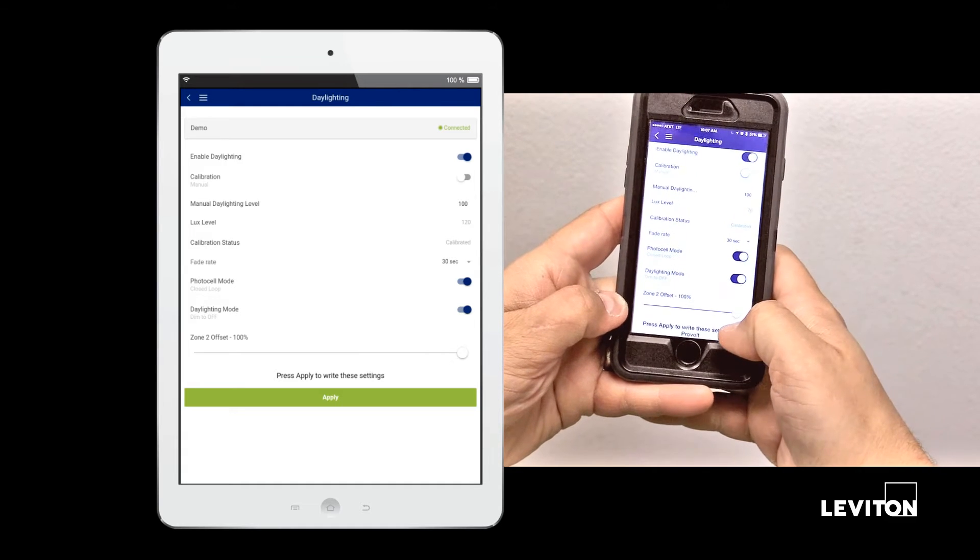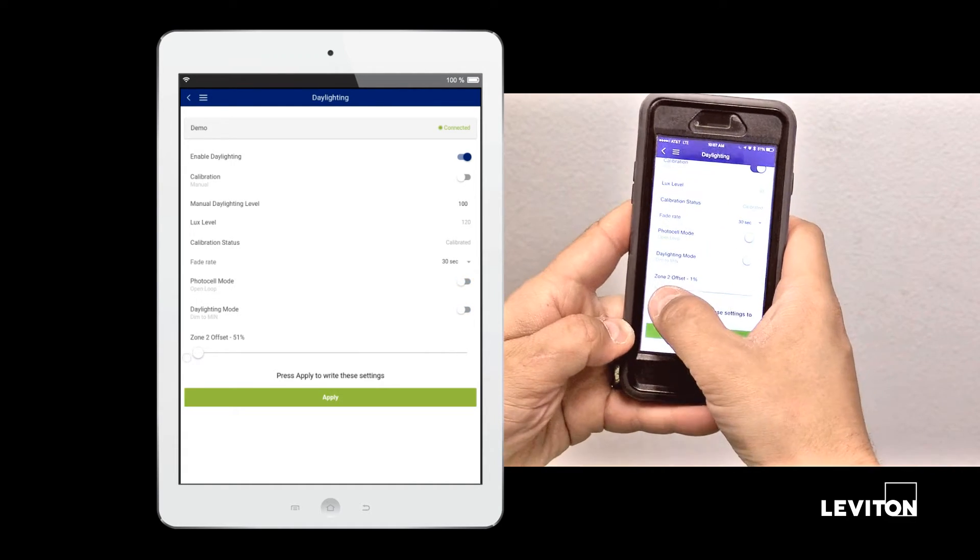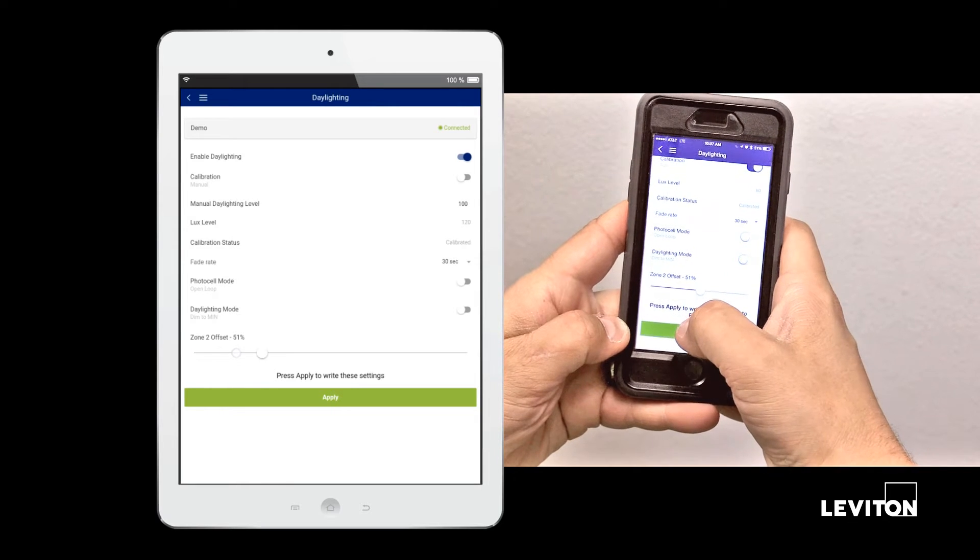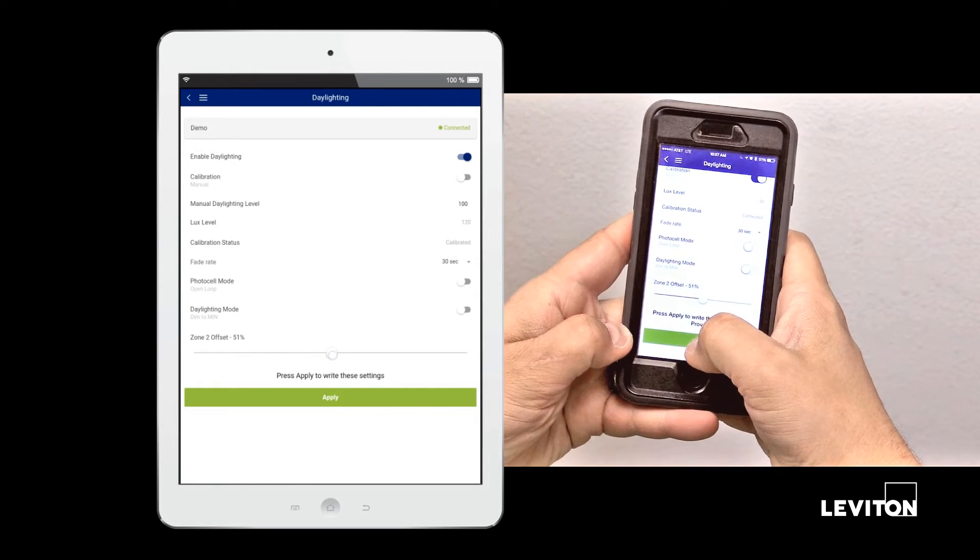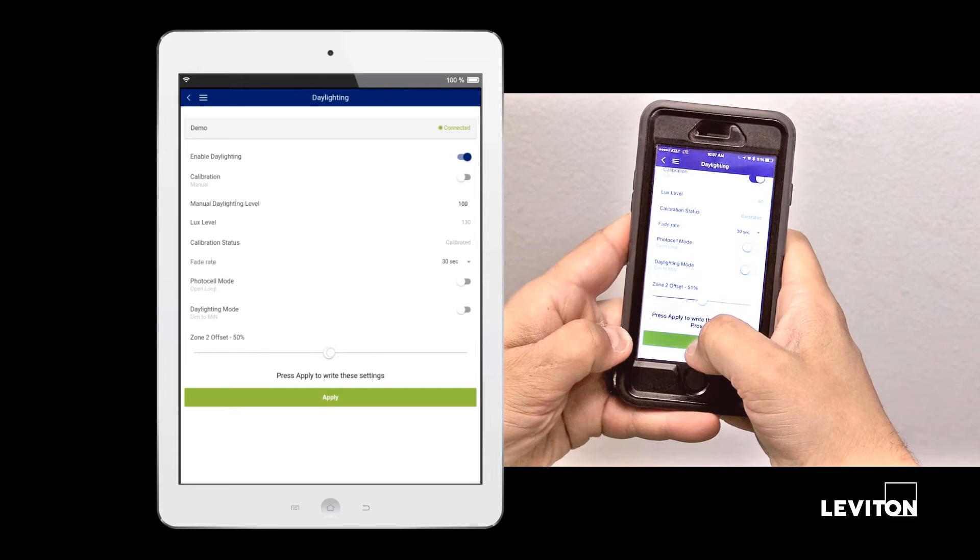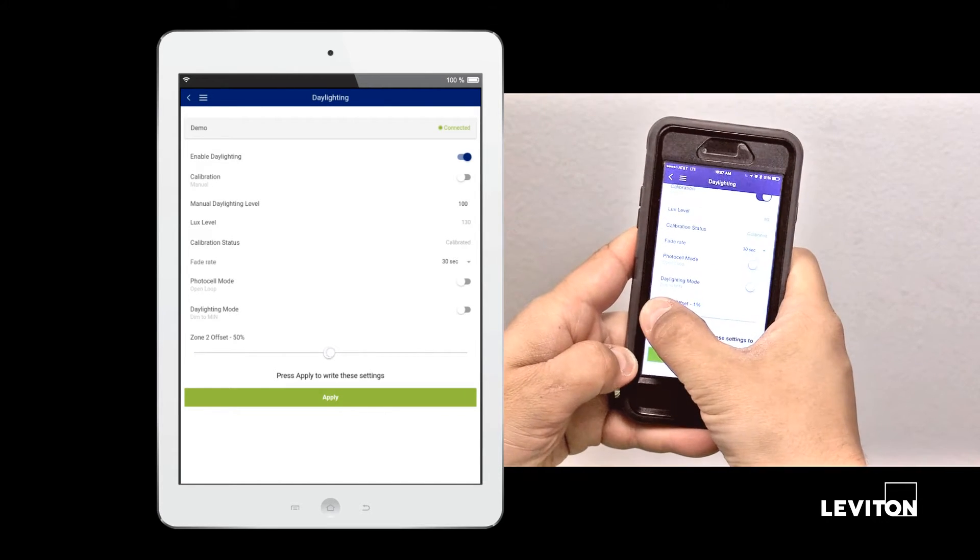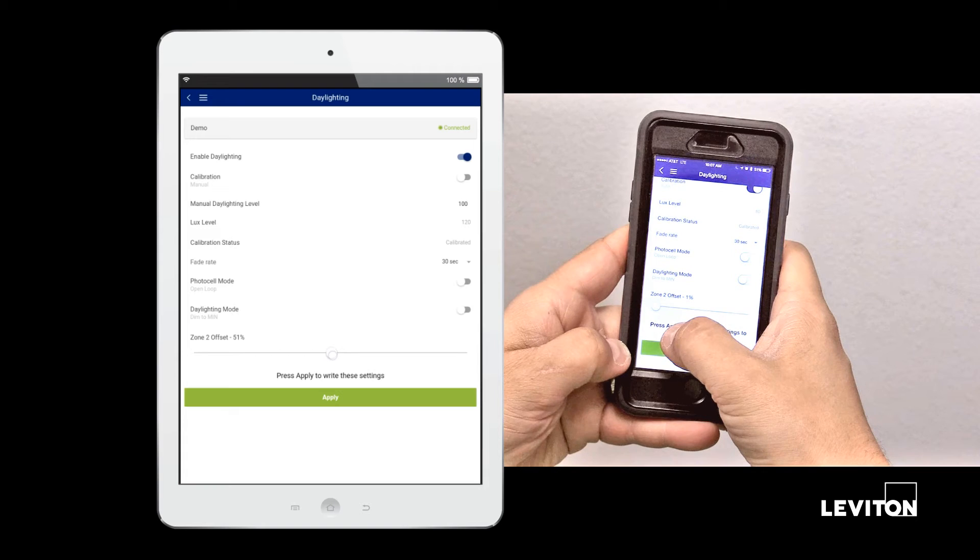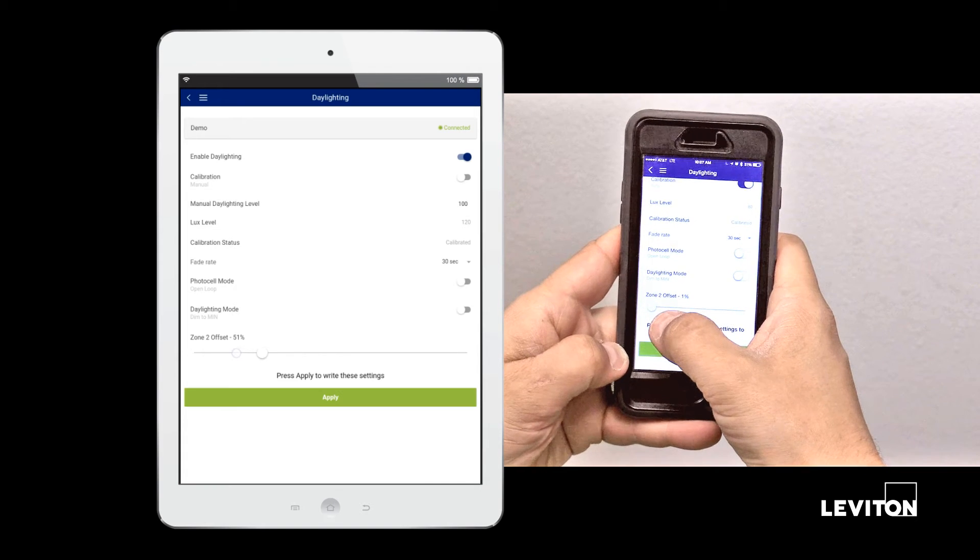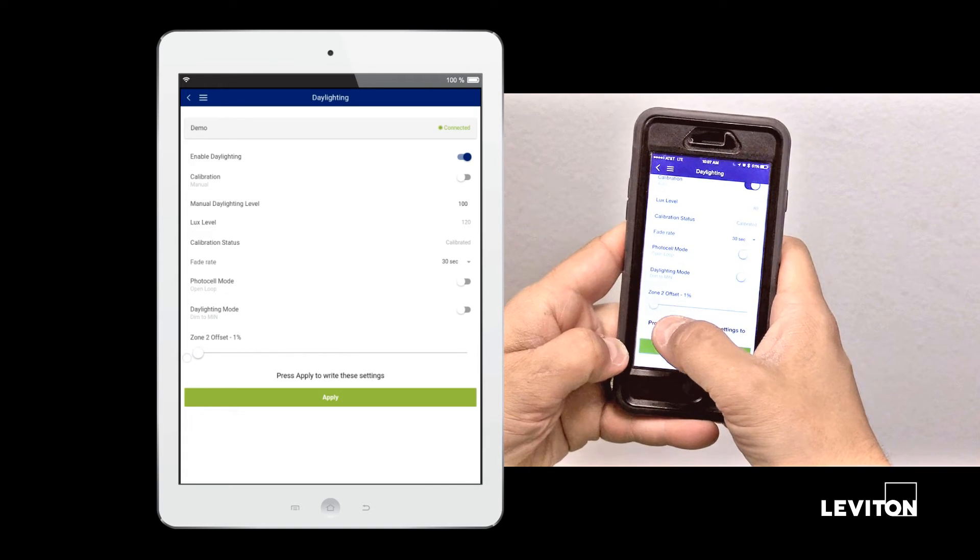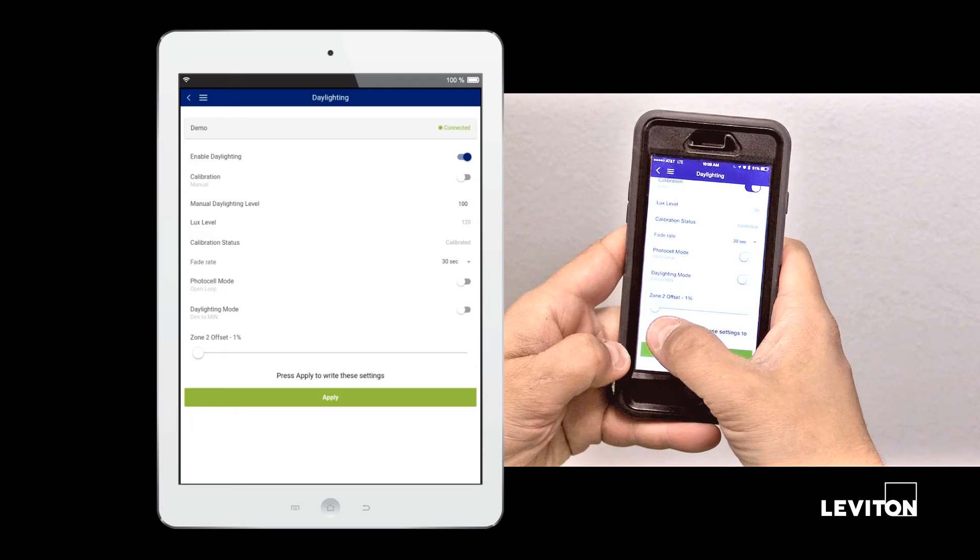Here you may also want to adjust your zone 2 offset. The greater the offset, the greater the difference between zone 1 and zone 2. Zone 2 will always be slightly brighter than zone 1 unless the offset is at 1%. This offsets the secondary zone to account for it being further away from the window. This setting will be specific to the space and will require some adjustment during the installation process.